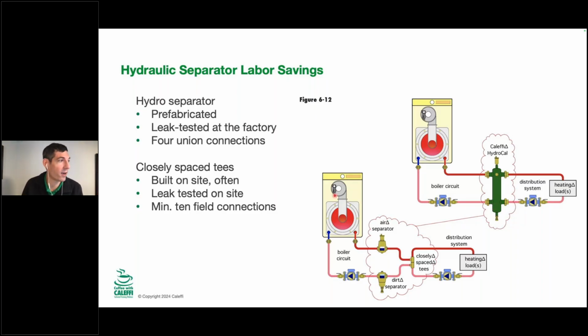And that's what I wanted to kind of cover here, that there's no perfect answer for this, but know that if you're going to do air separator, dirt separator, and closely spaced tees, if this is press or sweat or hemp or whatever your connection system is, you're going to have 10 connections that you either do on your workbench or you do out in the field, with potential for them to leak. Hopefully not. I know that everybody on this call who's listening to this webinar is likely capable of making all these connections without a leak. But you need to look at the labor required to do that to get a true comparison.